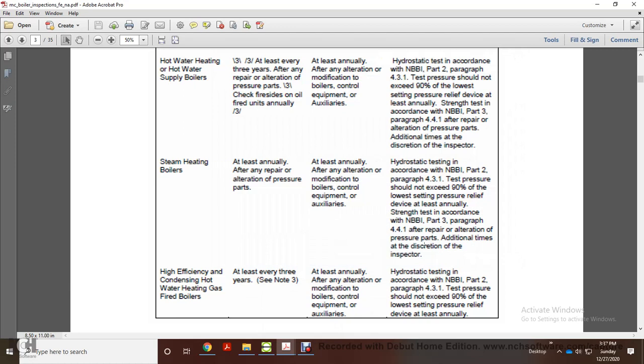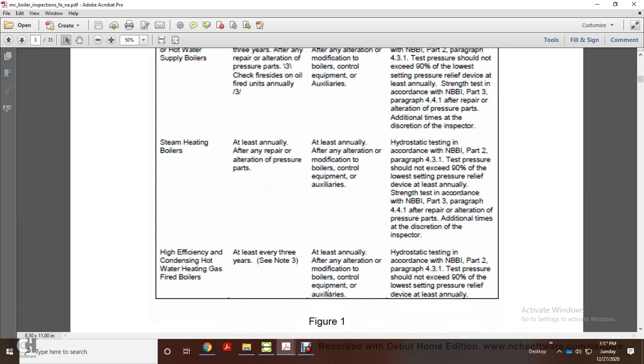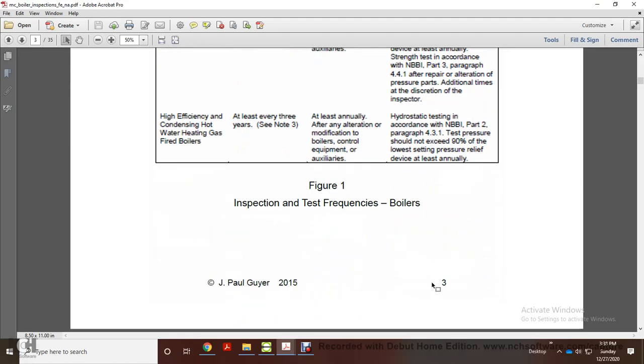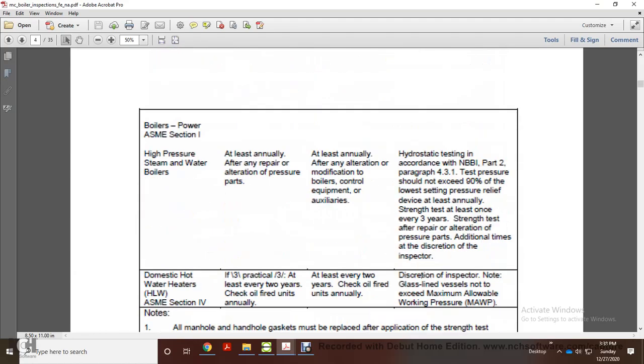After repair or alteration of pressure parts, and at additional times at the discretion of the inspector. High efficiency condensing water heating gas fired boilers: inspection at least every 3 years, and at least annually after any alteration or modification of boiler, controls, equipment, or auxiliaries, for external operational tests. Hydrostatic testing according to NBBI Part 2, paragraph 431, test pressure should not exceed 90% of the lowest setting of the pressure relief device, at least annually. High pressure steam boilers: inspected annually, and after any repair or alteration of pressure parts or boilers, controls, equipment, and auxiliaries. Hydrostatic testing per NBBI Part 2, 431, test pressure should not exceed 90% of the lowest setting of the pressure relief device, at least annually.